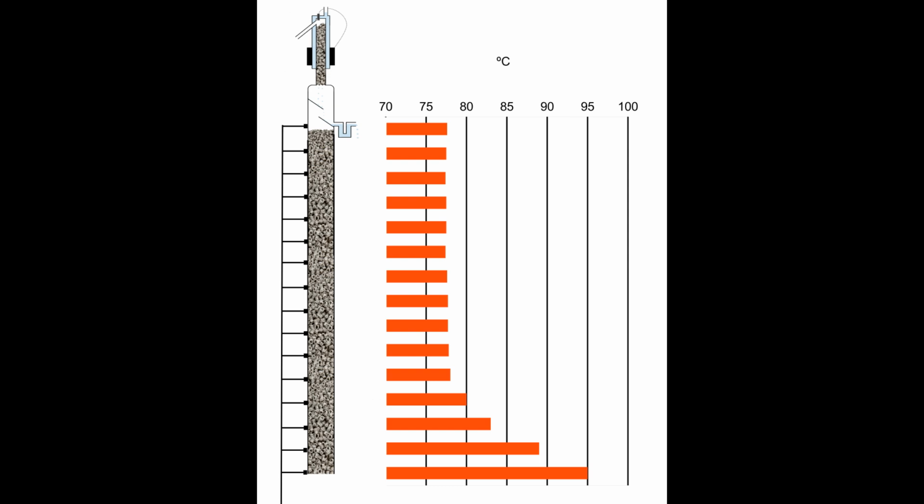This top temperature change is more sensitive than bottom temperature change, which is why the control parameter is a function of both the column top temperature and the length of the isothermal section. You end up using just the top and bottom sensors of the isothermal section, so strictly you might think you don't need the others, but they are informative in the process of setting up and tuning the column, so I would keep them. The surface temperature sensor system is forgiving because it depends on temperature differences of several degrees rather than several millidegrees, but it's not perfect.